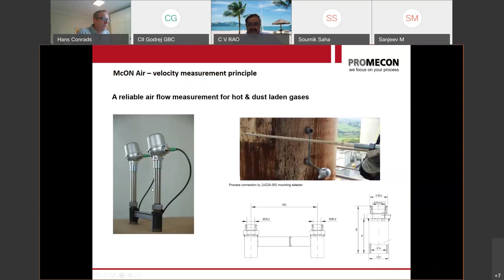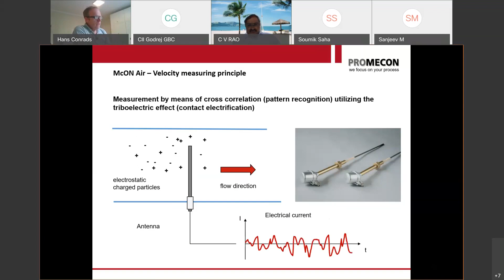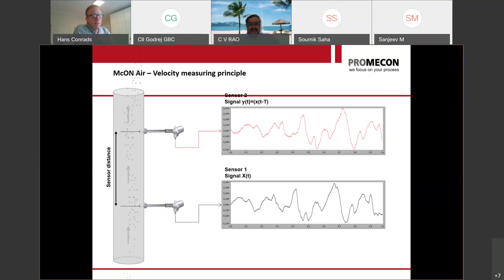You have a duct, and in this duct, you have charged particles. These are the ash particles coming from your air heater. These are the particles that are your problem with the delta P measurement system. With our sensors, we are measuring the electrification of these particles. And as more particles pass by one sensor, we can see more electrical current being induced on that sensor. Now, as we use two sensors in series, we are inducing an electrical current on two locations. You can see with your own eyes that these two signals are very similar.